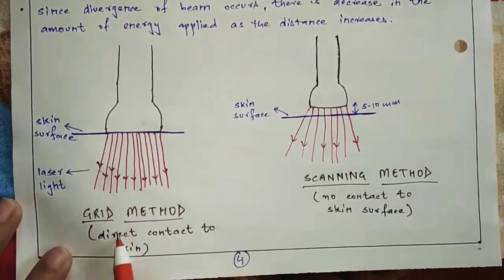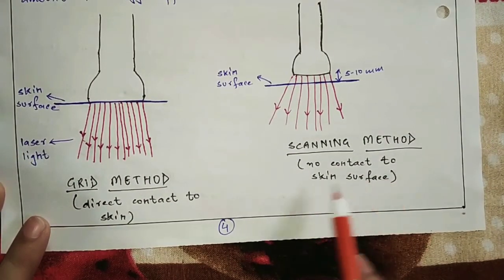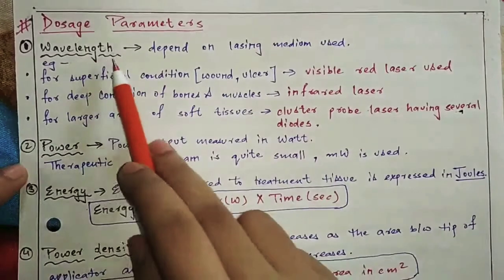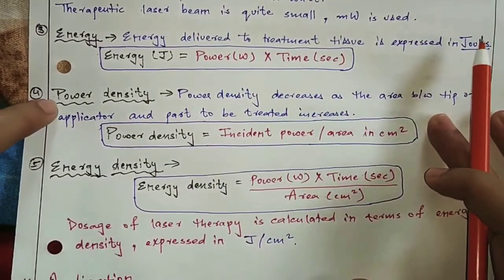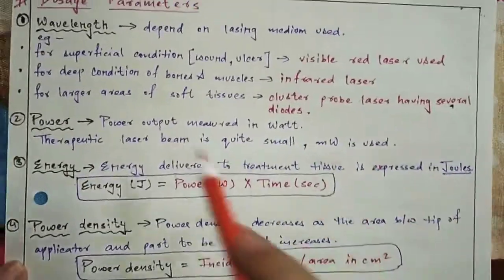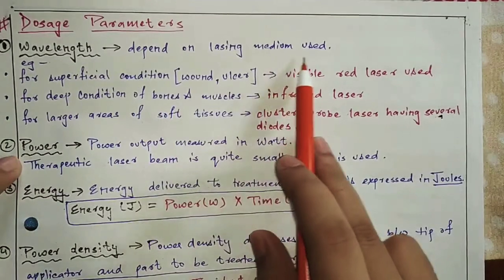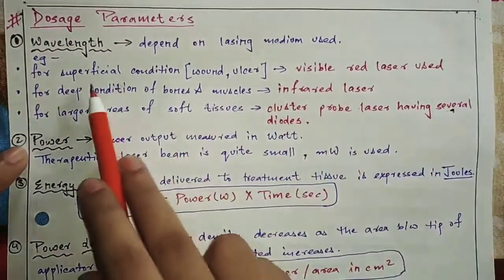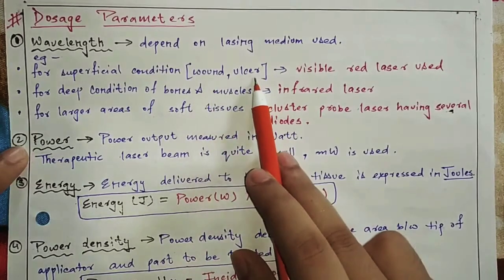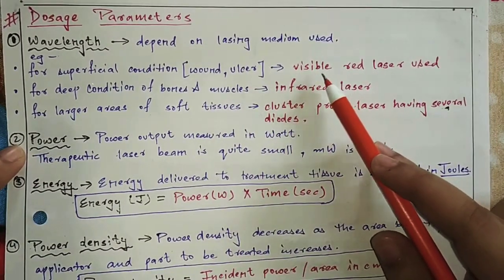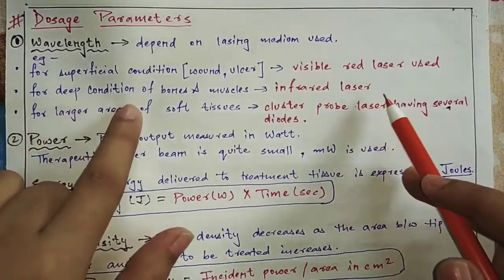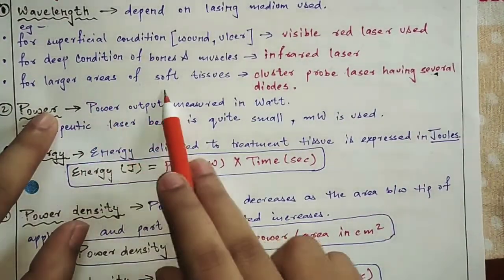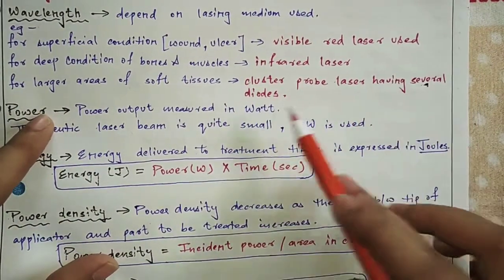Now let's talk about the parameters. We will discuss wavelength, power, energy, power density, and energy density. The wavelength depends on the lasing medium used. For superficial conditions such as wounds or ulcers, we use visible red laser. For deep conditions involving bone and muscle, we use infrared laser. For large areas of soft tissue, we use a clustered probe laser having several diodes. Power output is measured in watts, but for therapeutic laser use, we use milliwatts.